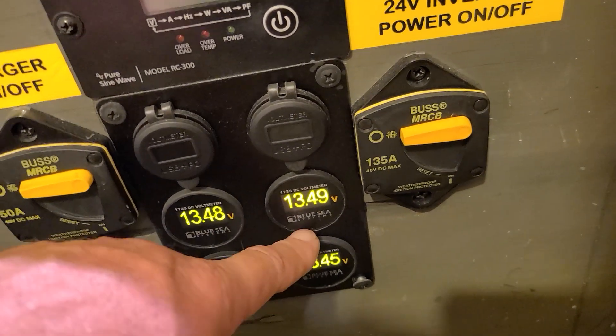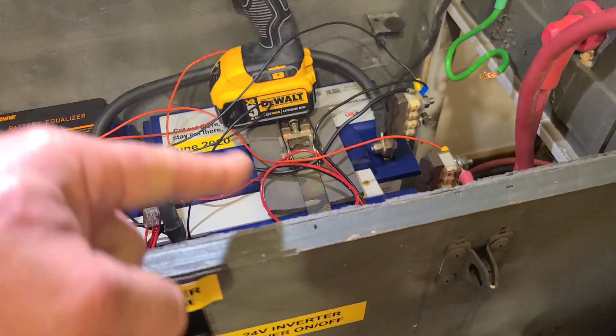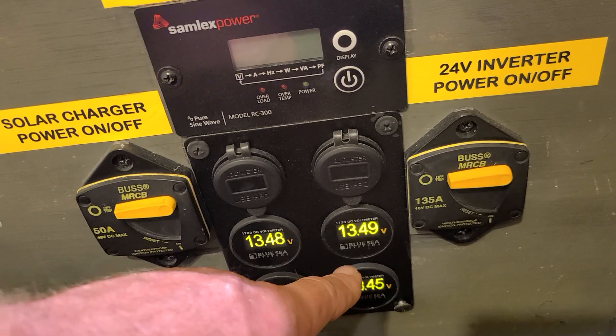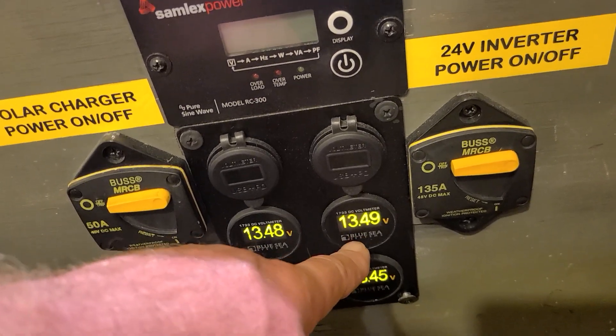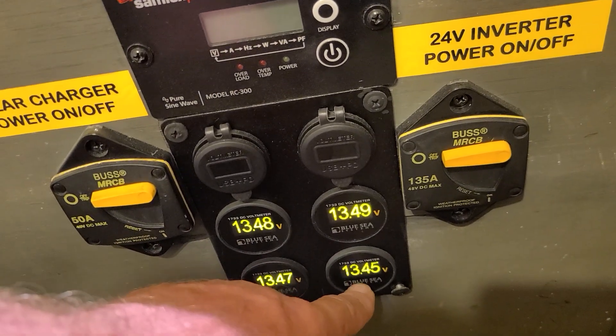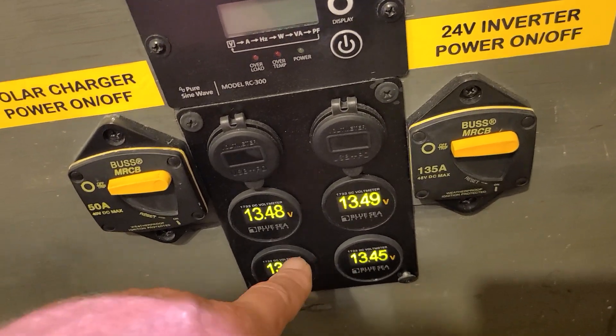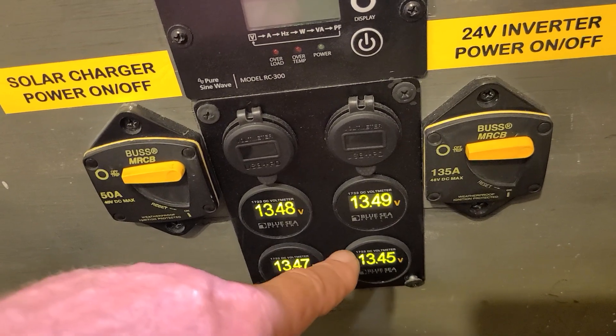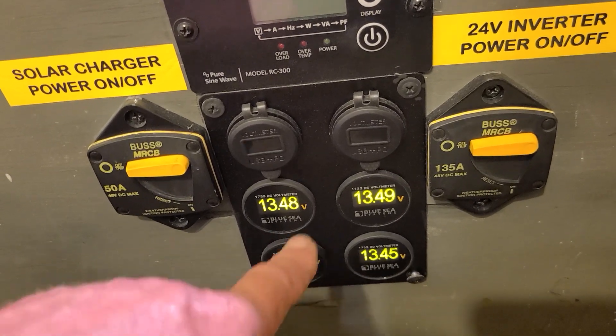This string right here — these two batteries right here — were all jacked up. We're talking this one was about 13.8 volts and this one was about 13.2 or so. Now look at them after about half an hour — these are almost balanced out and equalized.